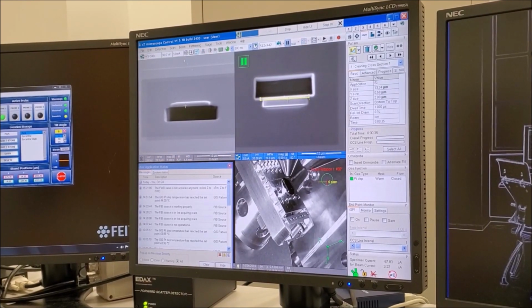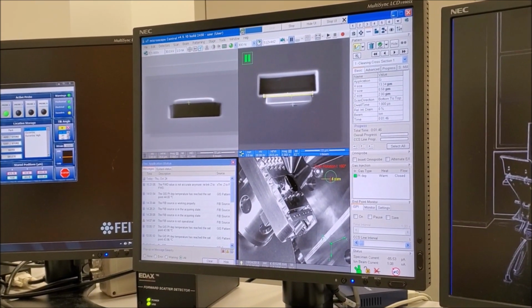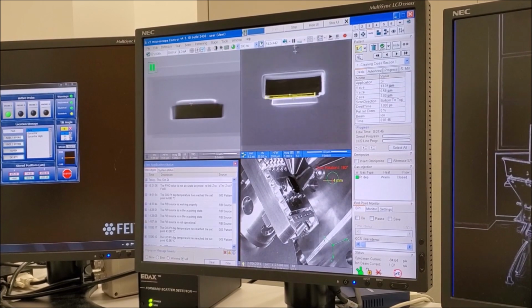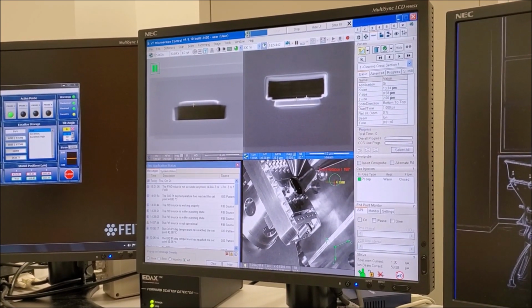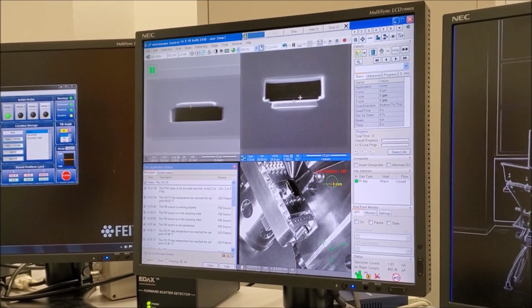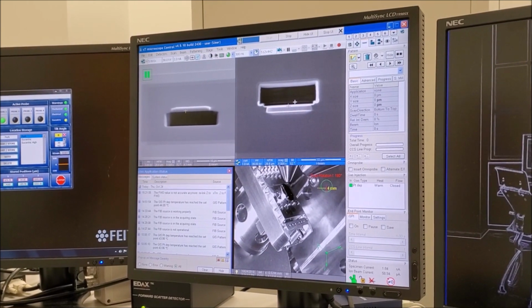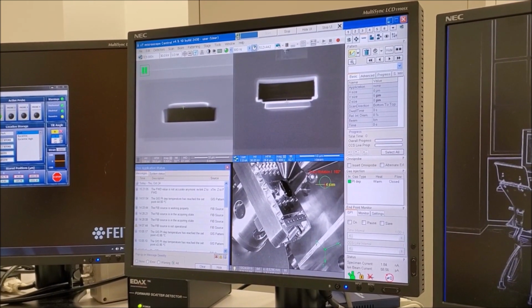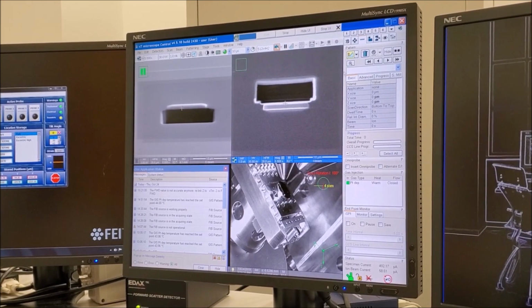To execute a rectangular mill, activate the ion beam quad and adjust the current as needed. Then unpause the image, delete any patterns that may be present, perform auto contrast and brightness, and focus as needed. Acquire a snapshot of the ion beam image.